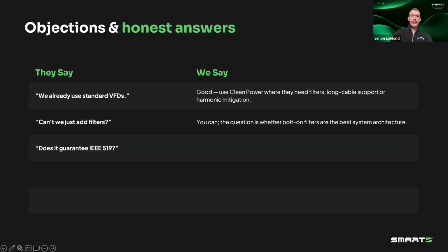Do you guarantee IEEE 519? Well, really, that's a misnomer because you're not guaranteeing IEEE 519 at the device level. And I still see a lot of specs that ask for a product that is IEEE 519 compliant at the device level. This is a system level standard.